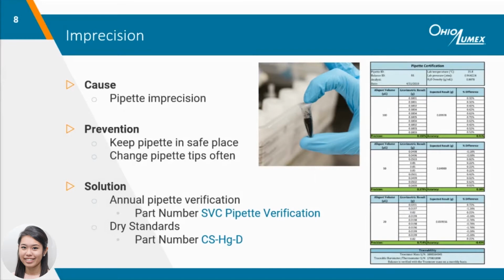Over time, pipettes can come out of calibration and cause imprecision. Having an accurate pipette is a fundamental part of analysis since incorrect volumes of standards can lead to difficulty achieving a linear calibration or bias your sorbent trap measurements. It's important to store the pipette so it stays safe and stationary. Leaving the pipette in a drawer where it can roll around can potentially damage the pipette. We recommend sending in the pipette with your M324 annual service to go through an extensive check to ensure the pipette volumes are within specifications or perform a linear offset if necessary.